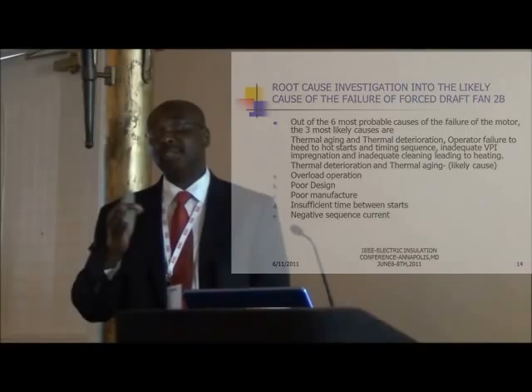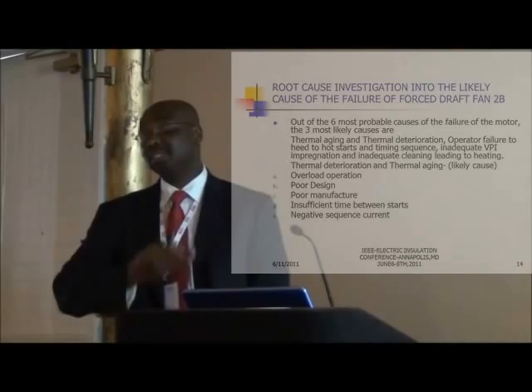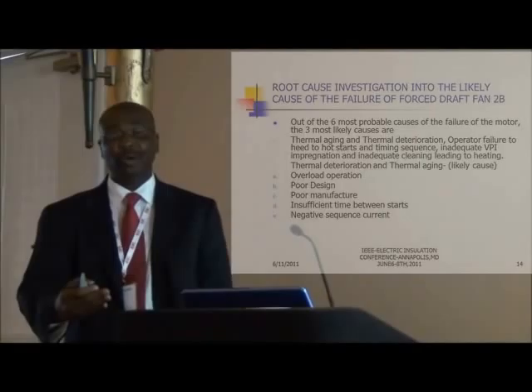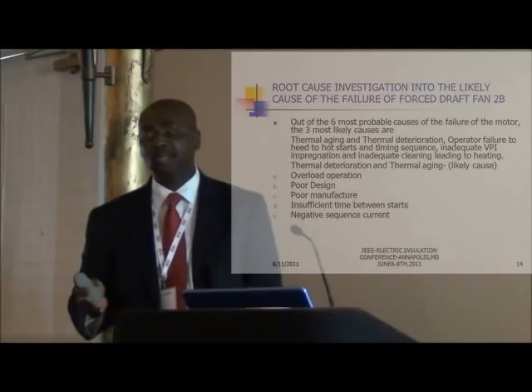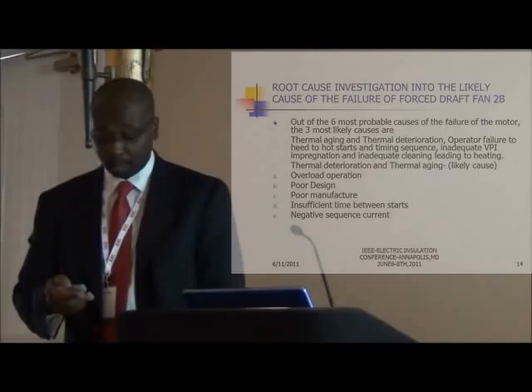When you start a motor, it creates five to six times the normal full load current. If you don't allow adequate time between starts, that heat accumulates and adds to the existing heat, leading to gradual degradation of the insulation. Additionally, a negative sequence current from an unbalanced condition is a concern — a 3.5% voltage unbalance can lead to a 25% increase in winding temperature.